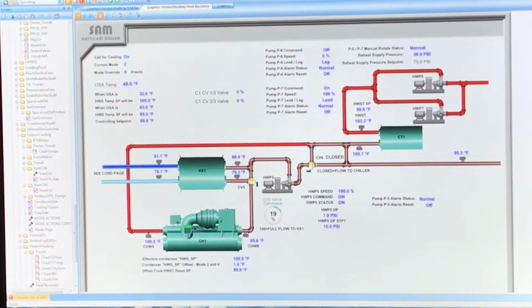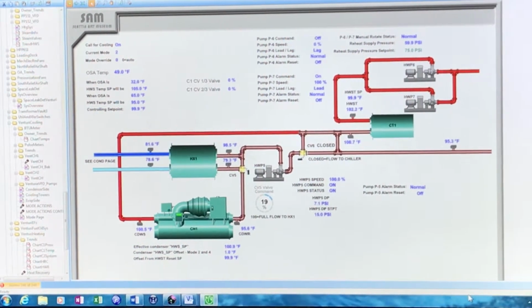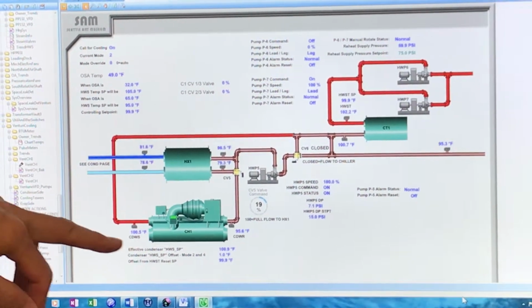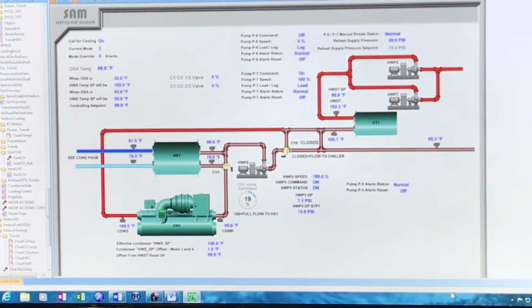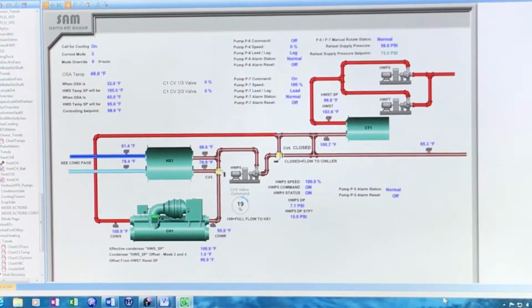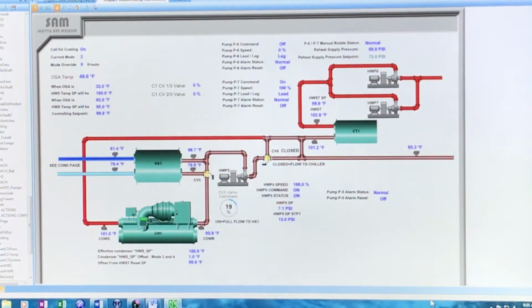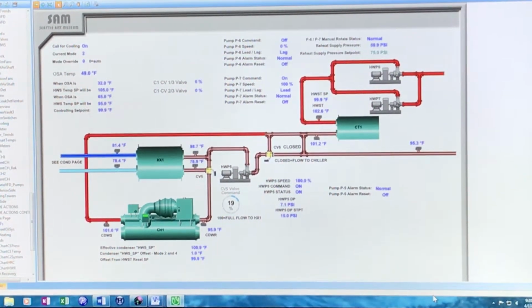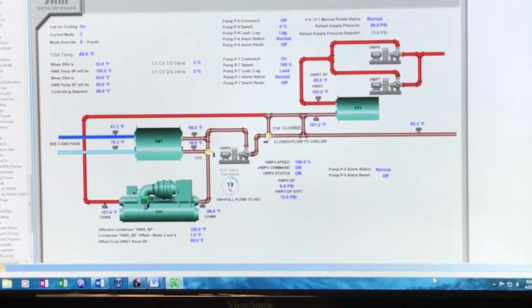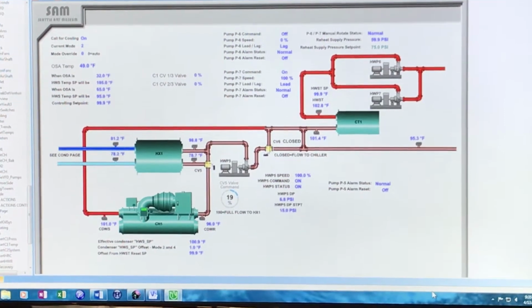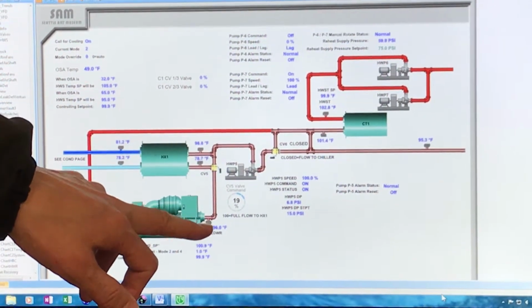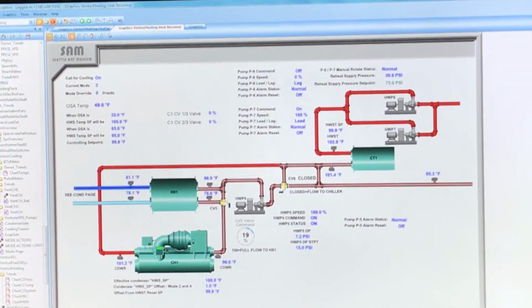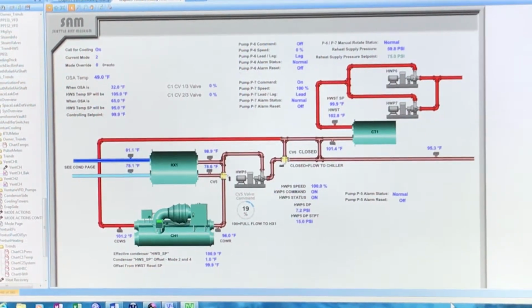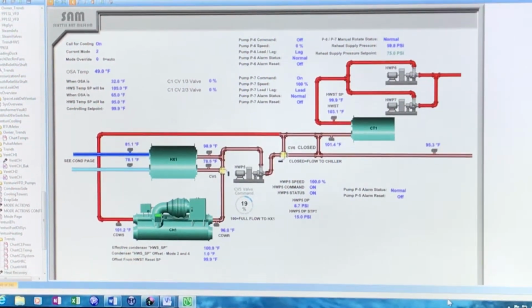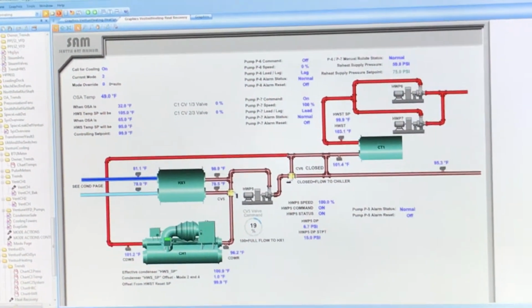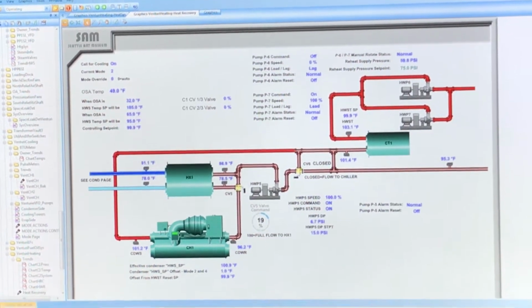I was discussing with the engineer, so we may be doing something that will track that supply temperature so that it will actually look at the capacity. If the chiller is running at like 50%, you may have more room for a higher leaving condenser water temperature. If it's running at 70%, you may have less room. Yeah, because you got to keep your delta P. Yes, because your return will then be lower, and you don't want your return to get above 102 or something like that, and that will not be good for the chiller either. So we'll look at the chiller load and see if we are tracking on that or limiting that. Then you will be able to push it higher when the chiller is running at a higher capacity.